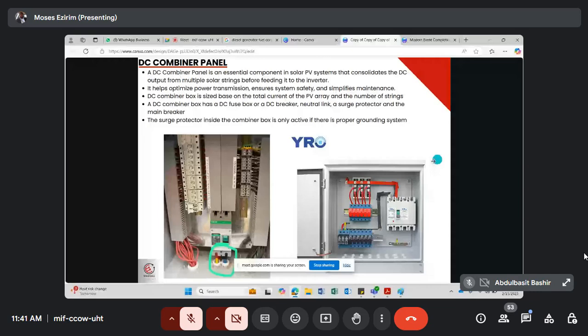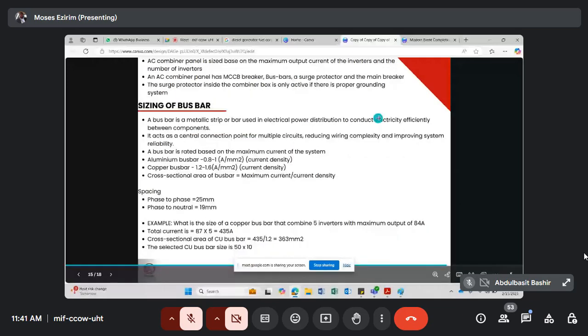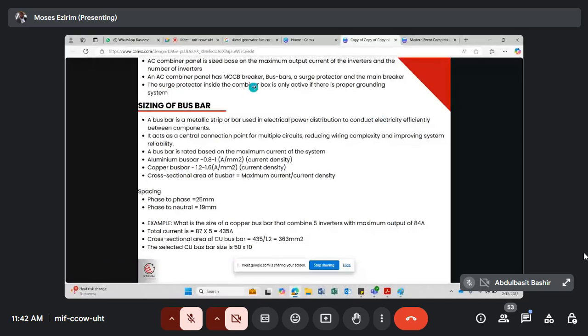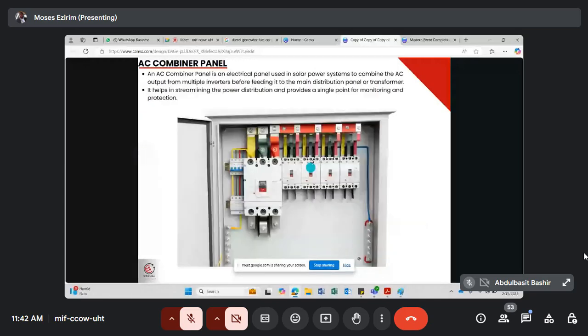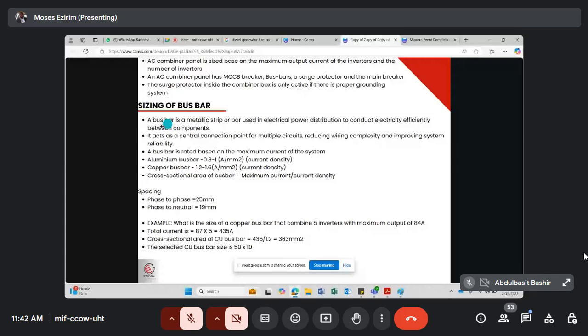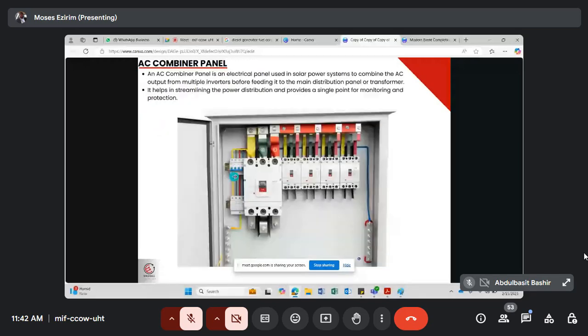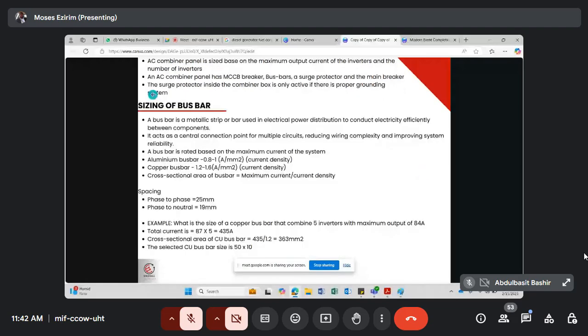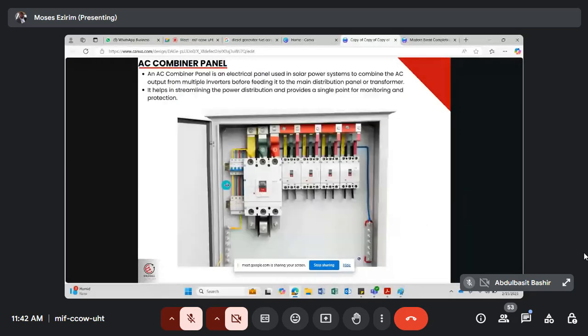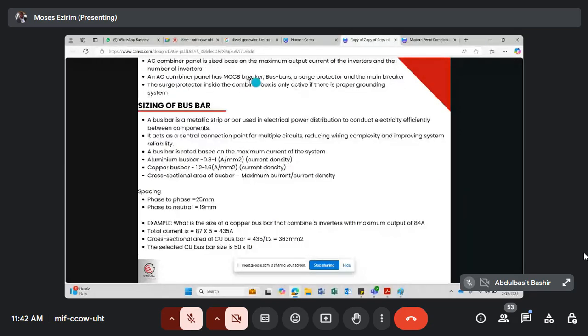All right. So now an AC combiner is sized based on the maximum output current of the inverter and the number of inverters. An AC combiner panel has an MCCB breaker, bus bar. You can see the bus bars here. A surge protector, you can see the surge protector. And breaker, you can see that here. All right. So now the surge protector inside the panel is only active if there is proper grounding.